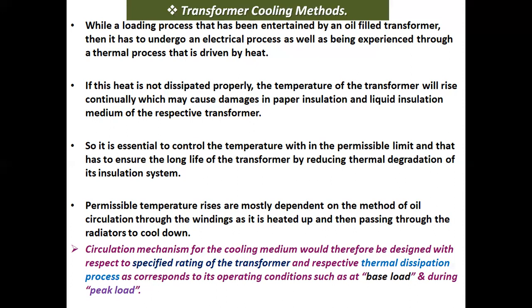Permissible temperature rises are mostly dependent on the method of oil circulation through the windings as it is heated up and then passes through the radiators to cool down. The circulation mechanism for the cooling medium would therefore be designed with respect to the specified rating of the transformer and the respective thermal dissipation process as corresponds to its operating conditions, such as at base load and during peak load.